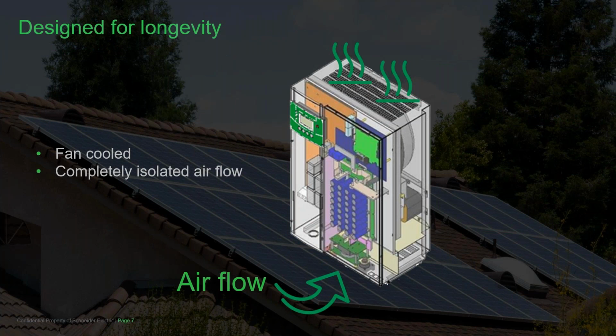XW Pro is an extension of the legacy XW and XW Plus models that have proven reliability in the field since 2006. Thousands of systems are still in operation with no end in sight. Part of the reason is due to the isolated compartment for airflow, which is unique to the XW platform. Dust can accumulate on circuit boards over time and inhibit cooling of components. Some dust may even have conductive properties that may lead to premature failure. XW Pro ships with a foam filter that mounts on the bottom just below the fan intake. In very dusty environments, such as wood shops, it is recommended to clean the filter regularly.